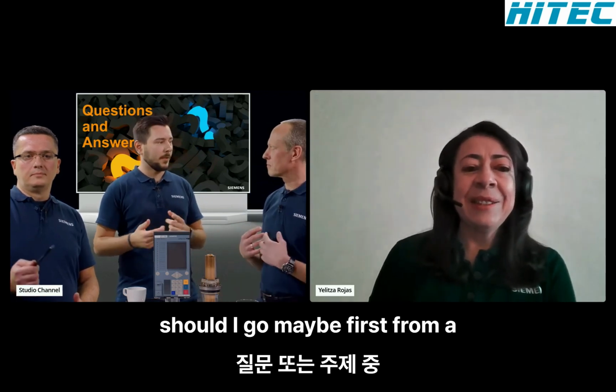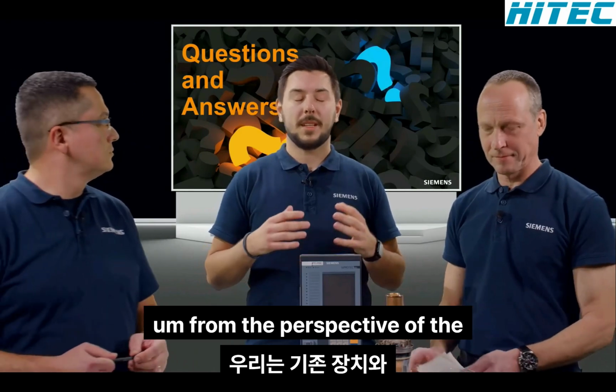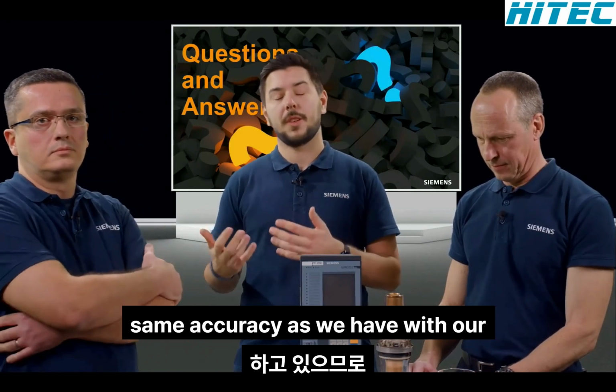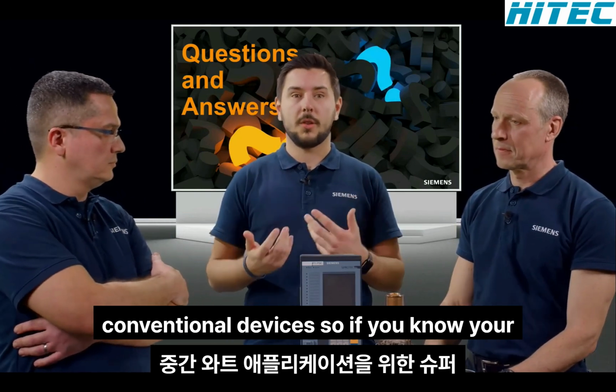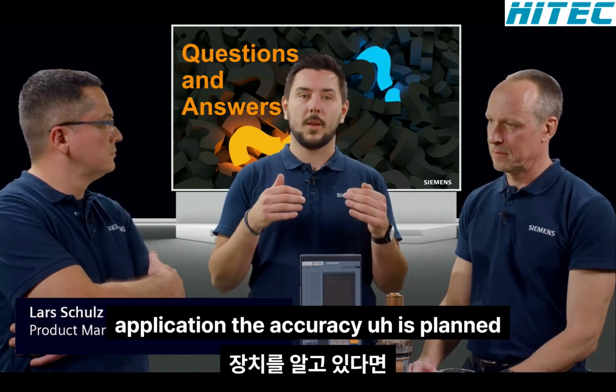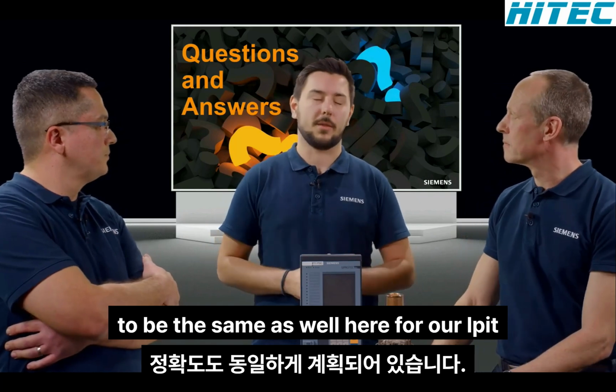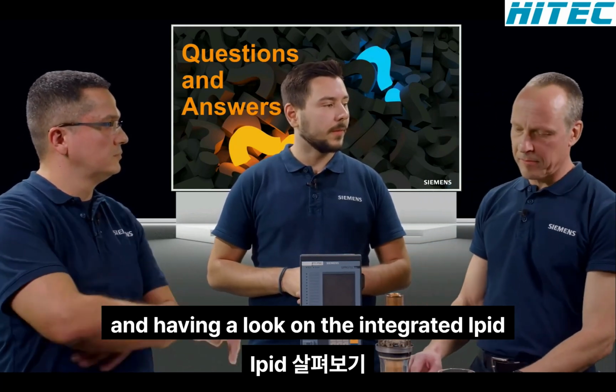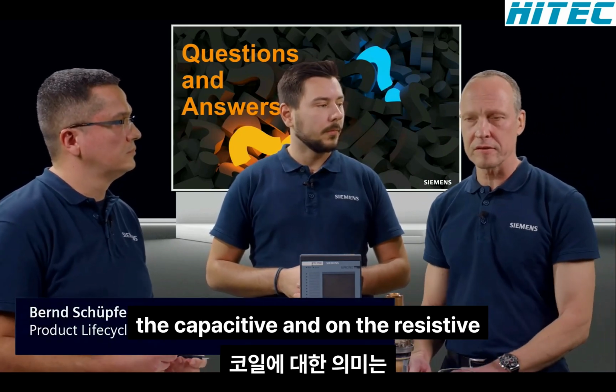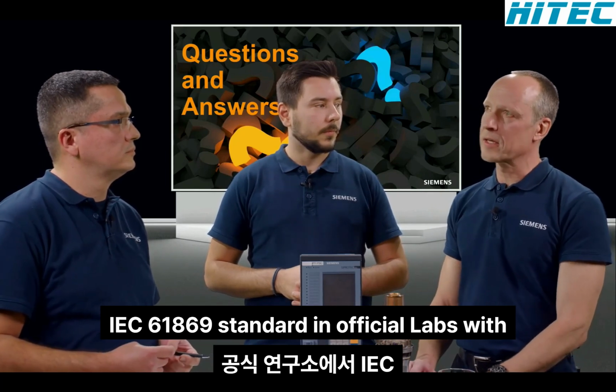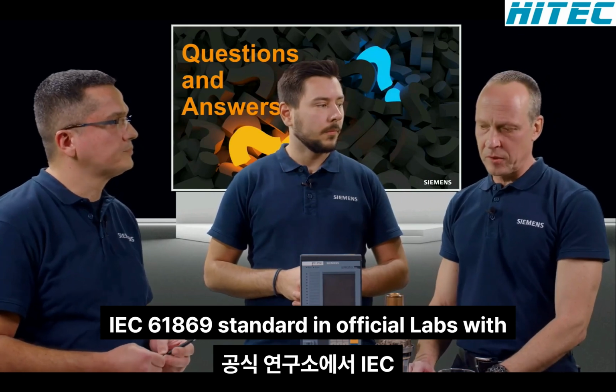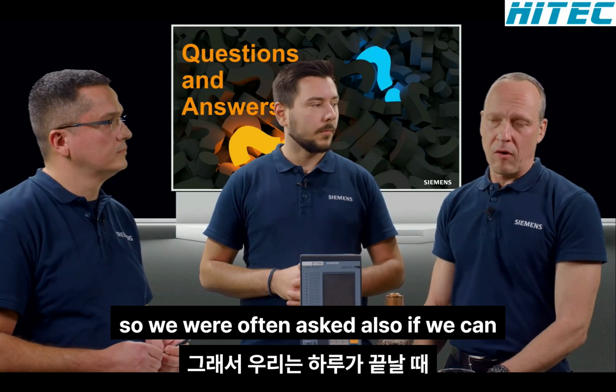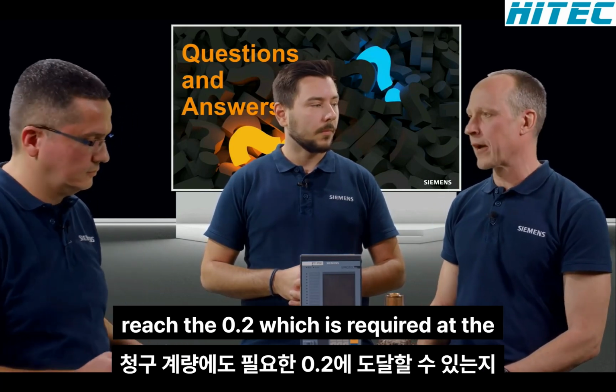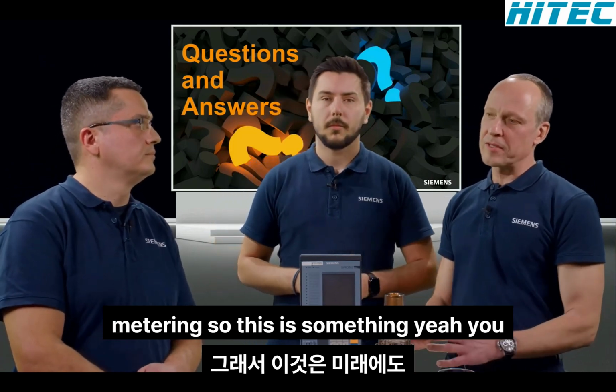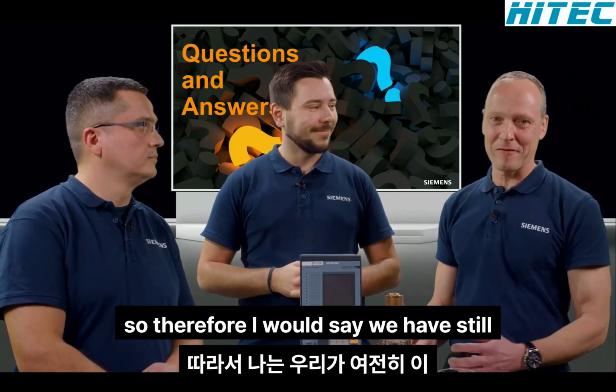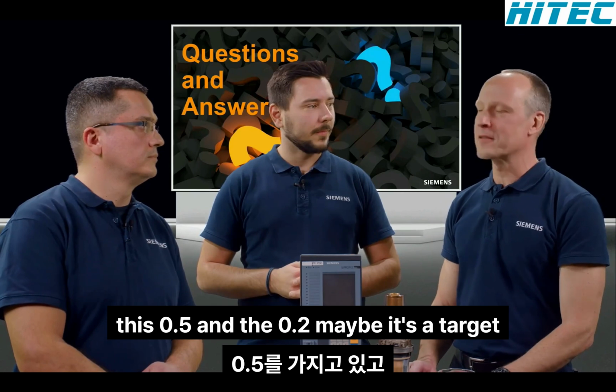Understood. Should I go first from a protection perspective and then you can take it up? Why not? So from the perspective of the protection device, we are aiming for the same accuracy as we have with our conventional devices. If you know your SIPROTEC 5 devices for medium voltage applications, the accuracy is planned to be the same here for our LPIT solution. Having a look at the integrated LPIT, meaning the Rogowski coil, the capacitive and the resistive divider, we have tested them to the IEC 61869 standard in official labs with an accuracy class of 0.5. We were often asked also if we can reach 0.2, which is required at the end of the day also for billing metering. Right, this is something that poses some challenges also in the future. So therefore, I would say we have 0.5 now, and 0.2 is maybe a target for the future.